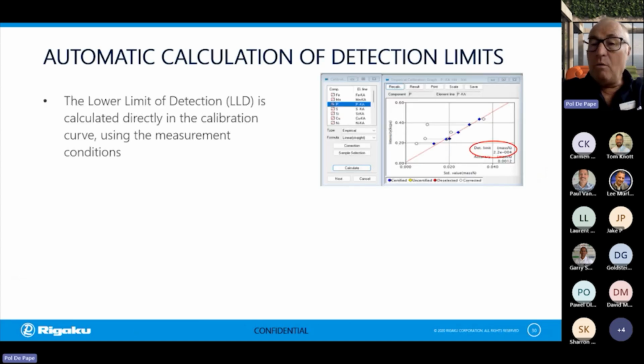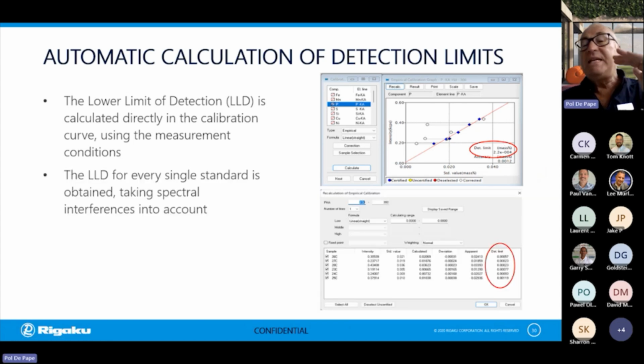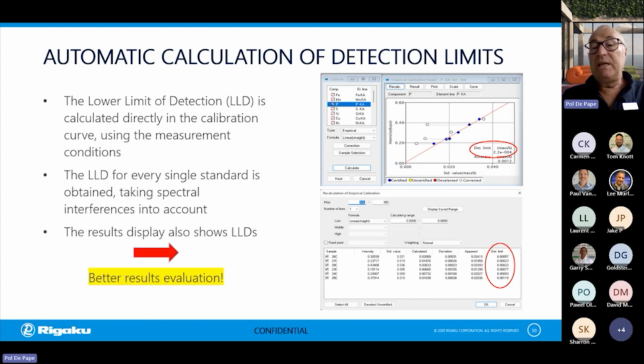Also, detection limits are now being calculated automatically. First of all, in the calibration curve, we can directly see what the detection limit is. In this case, we see a phosphorus calibration curve, and here we can see the detection limit. For each individual standard, the detection limit is also calculated. So the detection limit is not really specific only to an element. It is specific to an element in a certain matrix, and also to an element in a certain standard, because not all standards have the same composition. Therefore, the detection limits may differ depending on the standard composition.